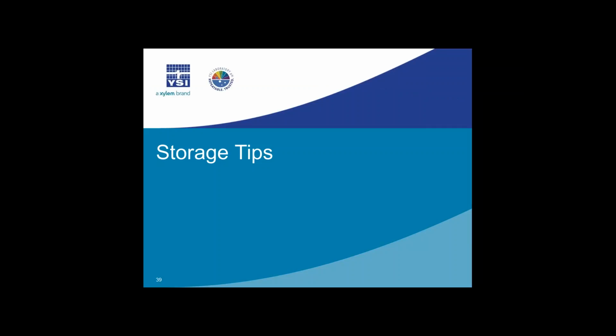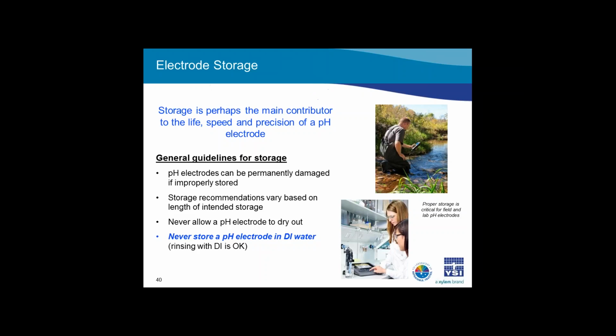Next, I would like to discuss how to properly store laboratory pH electrodes. Electrode storage is very important to extending the life of the electrode and electrolyte. If not stored properly, a pH electrode can be permanently damaged. We have 2 different storage recommendations based on how long you plan to store your lab electrode. I will review these in the next slide. Some helpful tips for all pH electrodes, whether lab or field, is to make sure that you never let your pH electrode dry out and never store your electrode in DI water.